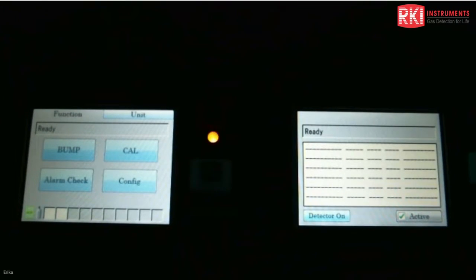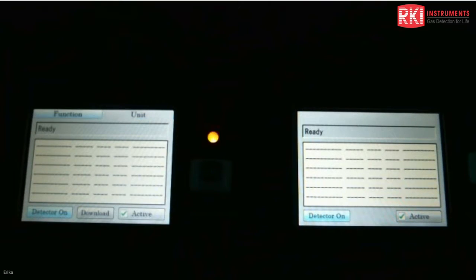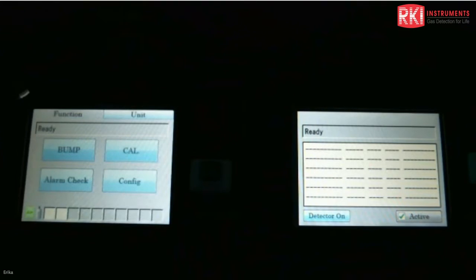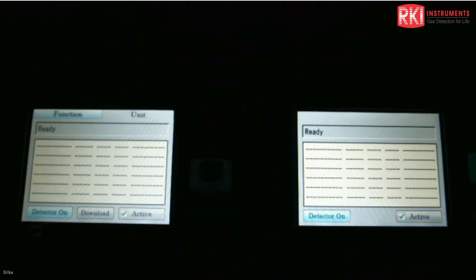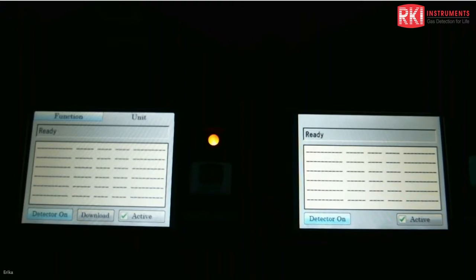So there's 2 tabs on the top where you can just touch it. There's the unit tab, and there's also the function tab. The function tab would have your bump, alarm check, cal, and configuration. Your unit tab would have the detector on, where you can turn the detector on and off. You have a download button. The download button is only good for the standalone mode if you have the SD card connected in there. So you can download information from your GX6000 to the SD card. And there's a little active button as well over there where you can check and uncheck it. Right now it's not really doing that because this isn't on.